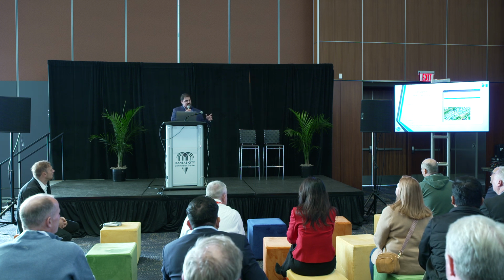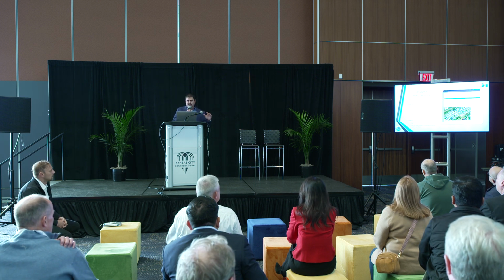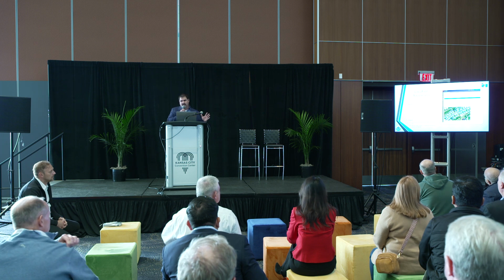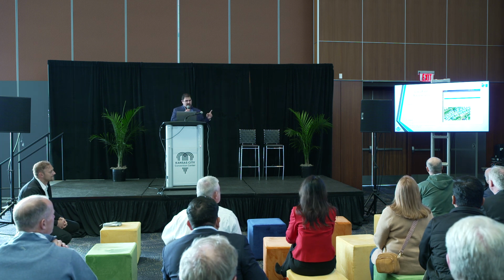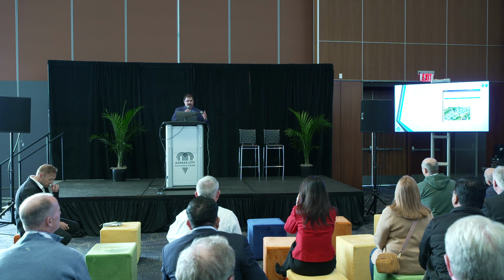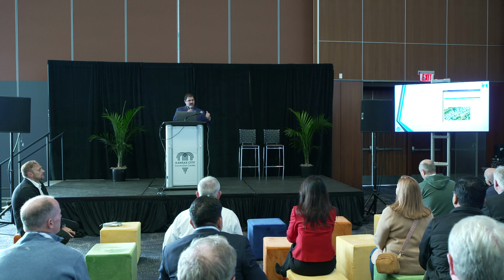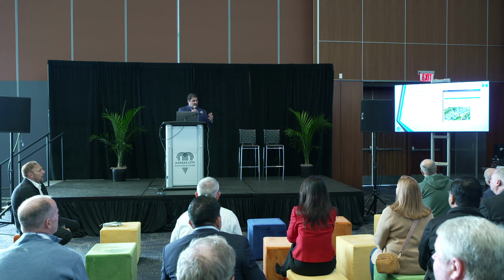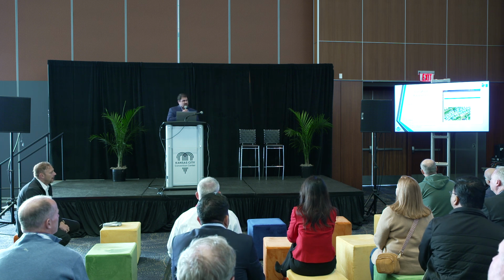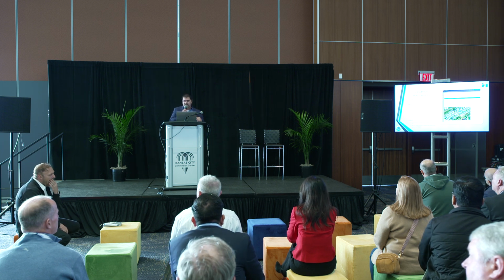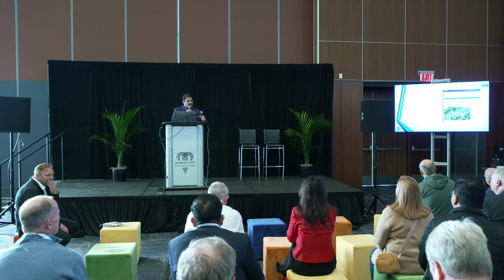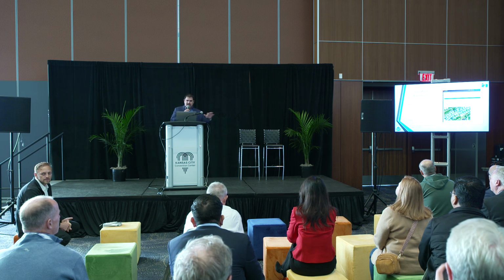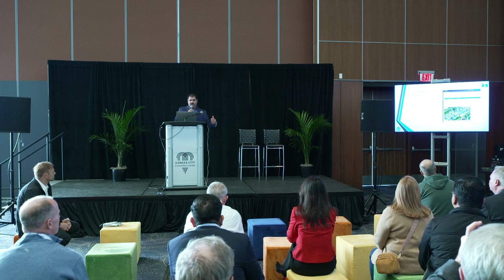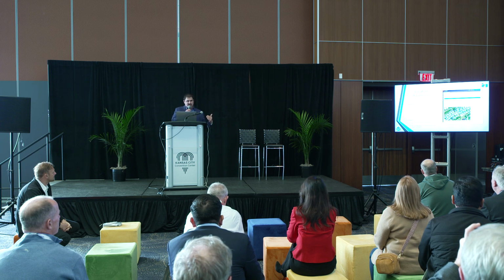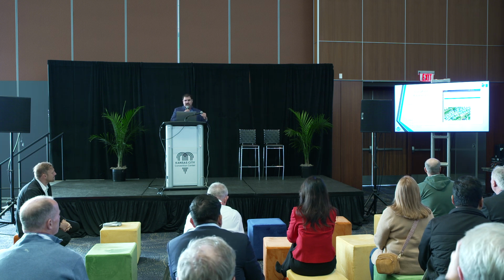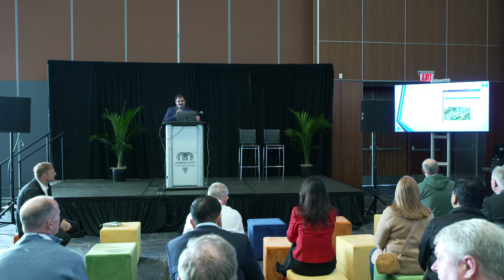So what this does is allow you to dynamically know the electrical connectivity of any transformer in real time. The meter itself has 900 megahertz, cellular options, PLC, and Wi-Fi. We leverage the PLC very uniquely to establish a communication link between all the electric meters on that same secondary circuit, so we can reach out and literally measure and touch every device on the load side of that distribution transformer, giving us confidence that everyone is electrically connected to the same distribution transformer.